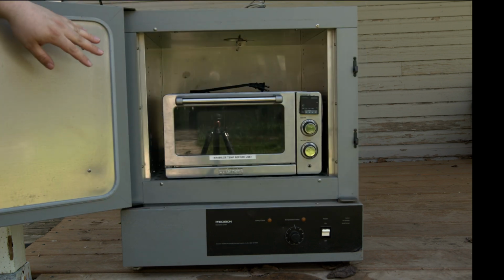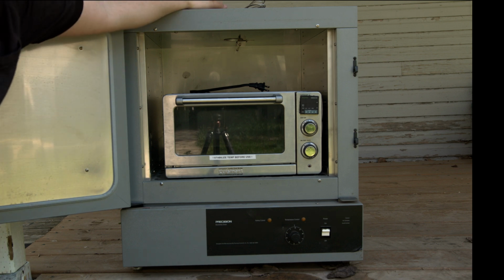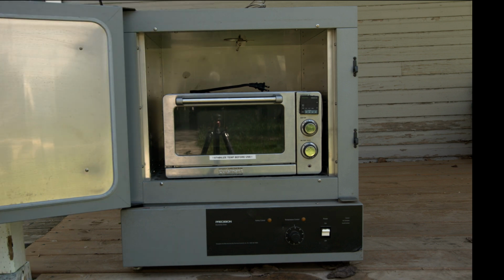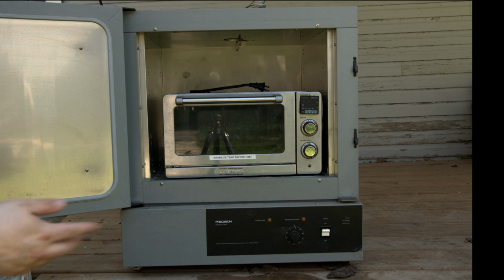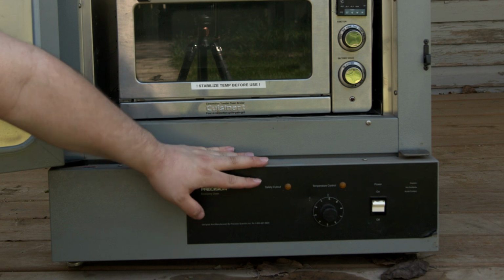It's a gravity convection oven, which means it just has a vent up here in the roof. No actual fan, so if you were like powder sample drying, that would be agitated by forced airflow. That would be a bad thing, so this just uses natural convection to actually heat up evenly. It is pure analog control, and that's what I'm going to be fixing today.